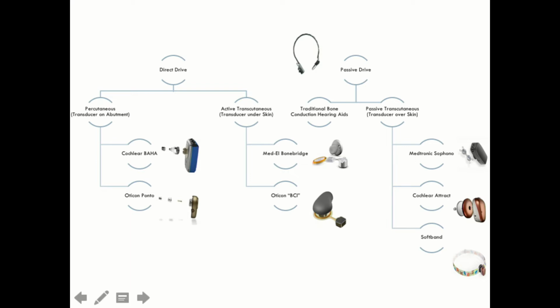The direct drive, specifically this percutaneous system, is what we utilize here at HSC. We use 2 different manufacturers. They're both essentially very similar. They involve the abutment, or the little silver ring that protrudes through the skin and then attaches to the device on the exterior. So just wanted to note, the sound is still generated from the outside in this area, but because of the physical attachment to the bone without the skin impeding that transmission, we get a very nice signal to the cochlea.